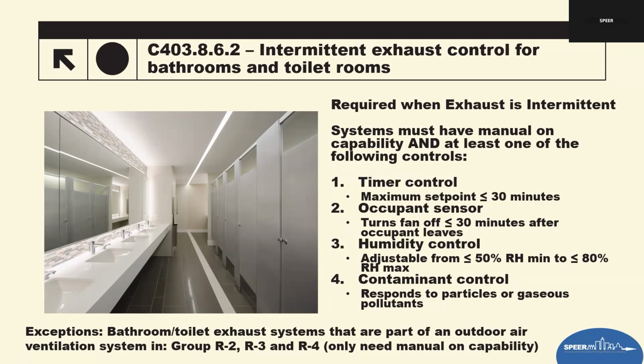Bathrooms generate moisture, odors, pollutants. These controls basically balance that indoor air quality with energy efficiency by ensuring fans only run when needed and not indefinitely. Plan review tips for this one is verify control type. Is it timer? Is it occupant sensor? Is it humidity sensor? Is it contaminant sensors? Confirm the limits and their settings. Is it equal to or less than 30 minutes for everything except humidity? And then the humidity is going to be between 50 to 80%. And then check whether occupancy exceptions are applied for. If they are, then verify that they are meeting those exceptions.